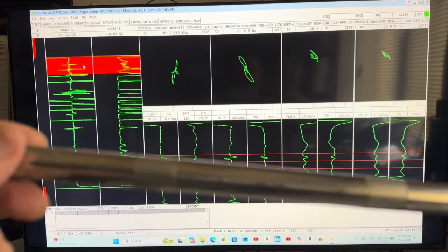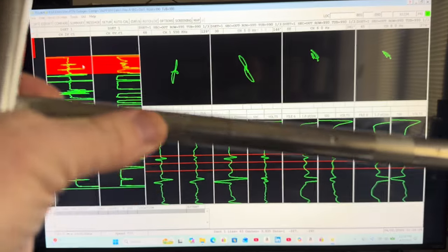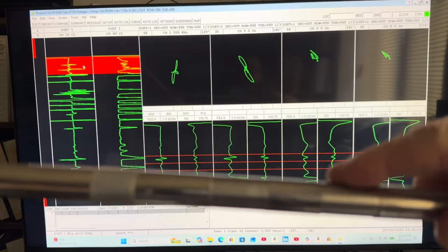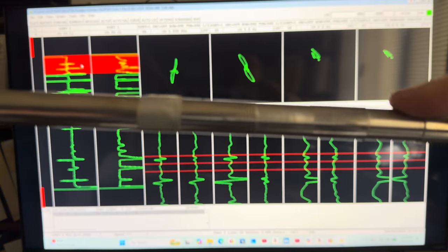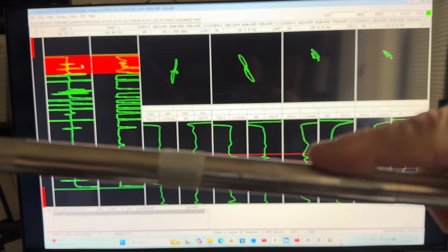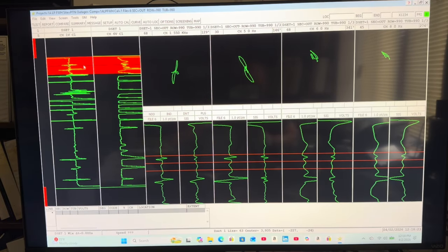Then I've got a cal standard here that's got some 360 degree, where is it? Yeah, here we got some 360 degree wear scars of different depths. But these calibration tubes, like I say, they're made in a machine shop and they have pretty much perfectly designed flat bottom holes or grooves that are very symmetrical.